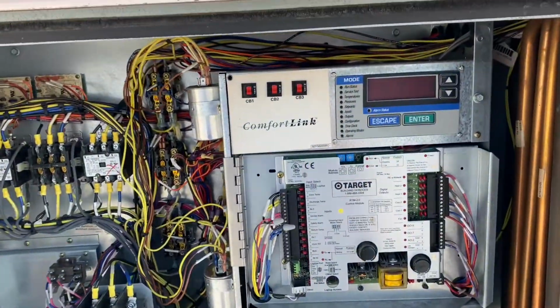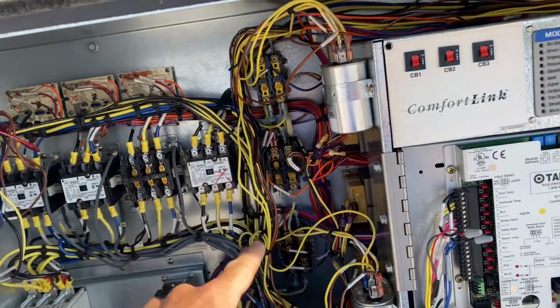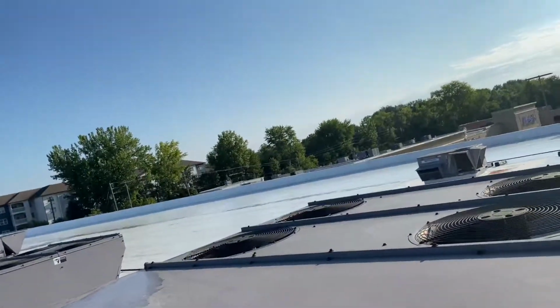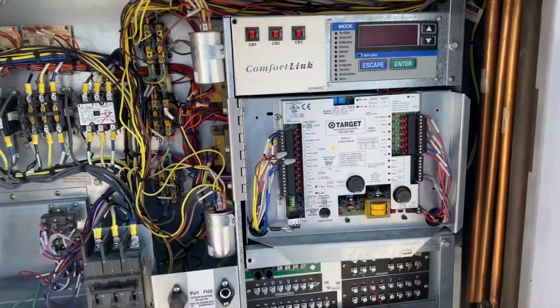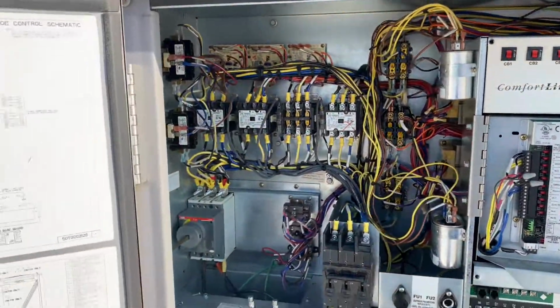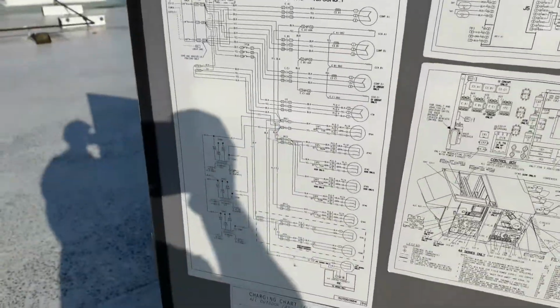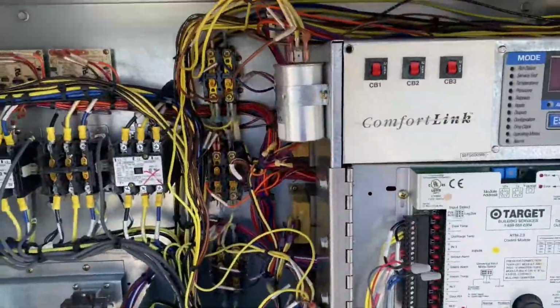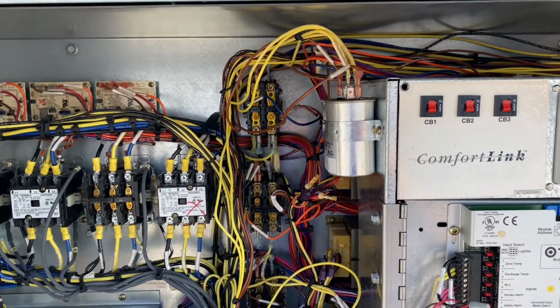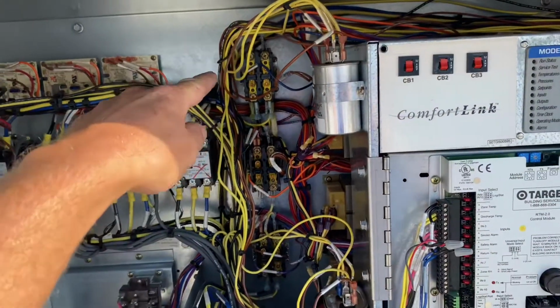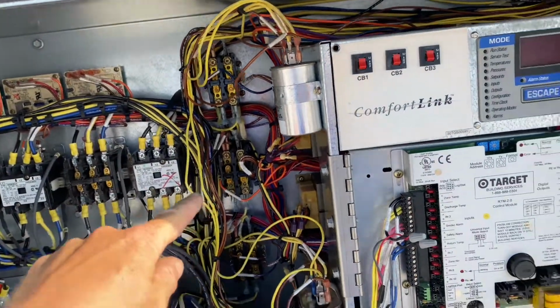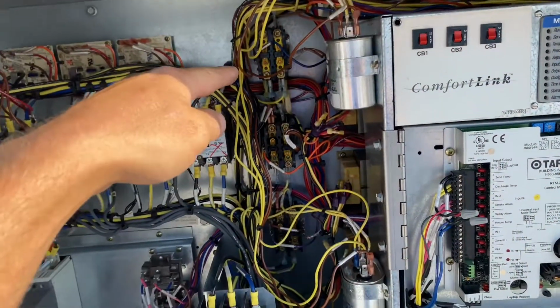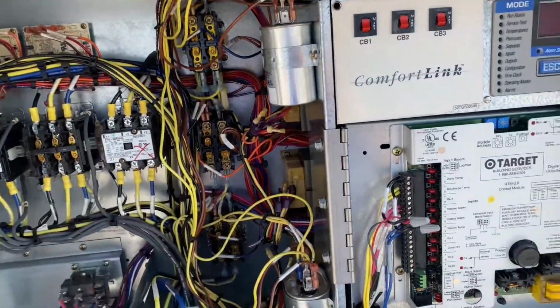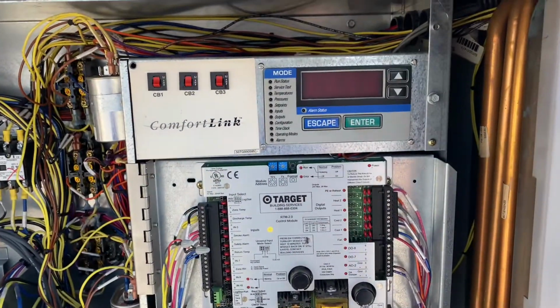So I'll go through them. It shows there's only 3 contactors, 1, 2, 3, and it has 4 fans. So one of the contactors is paired up with 2 fans. I'm pretty sure it's contactor 2. Go by the wire diagram. It's contactor 2. So contactor 2 should pull in fan 2 and 3. So it should go 1, 2, 3, 4. Or I guess I'm pointing at them wrong. 1, 2, 3, 4. So hopefully I can do that.